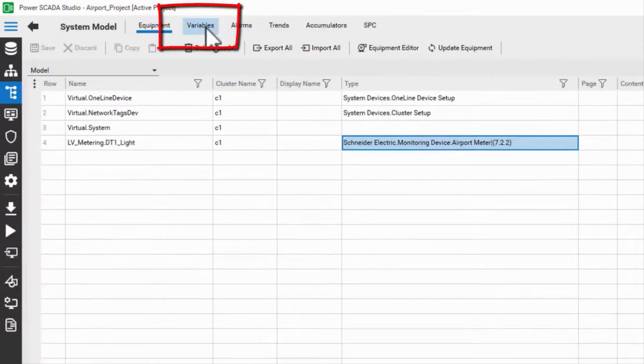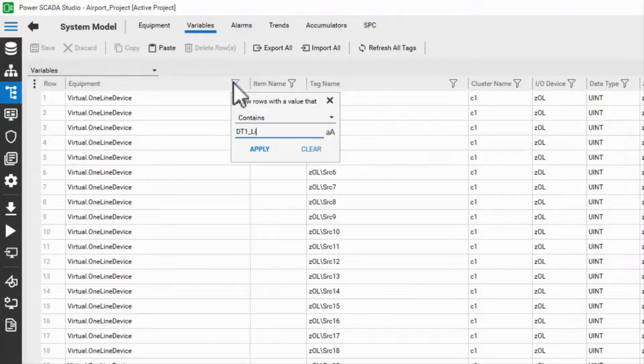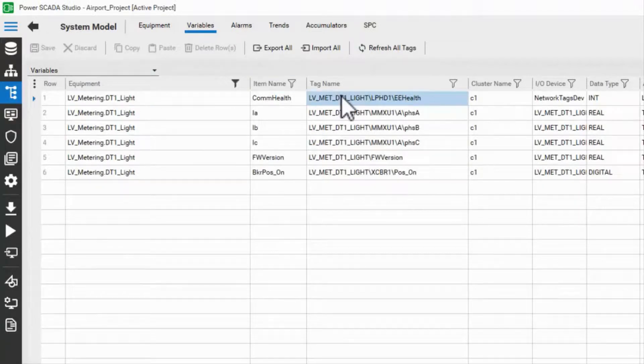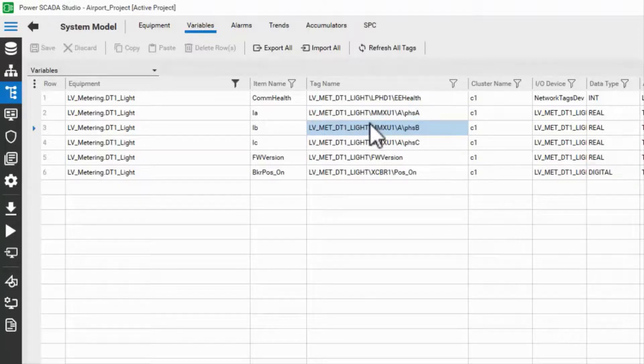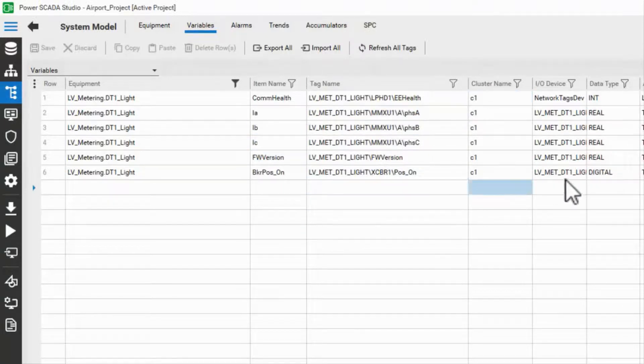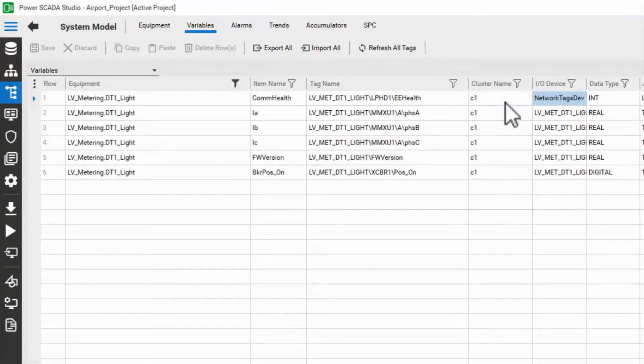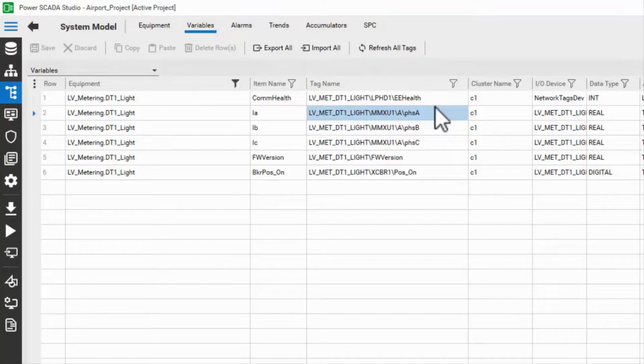Next up are the variable tags that we selected in the profile editor. The tag name is formatted as I.O. device slash tag name. We set the equipment and I.O. device in the I.O. device manager, and the rest of the fields come from the profile editor. The only other tag I'd like to point out is this EEHealth. It's associated with our equipment, but is read from a system device called NetworkTagsDev. This tag is populated by the I.O. server in runtime, and is used by the communication failure alarm. It's managed automatically by the I.O. device manager, and generally shouldn't be modified or removed.